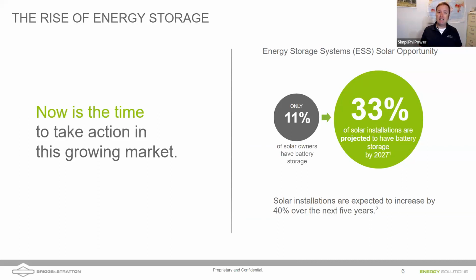That's anti-islanding, where you don't want to be producing electricity and sending it back to the grid when the grid is down, because you might electrocute a lineman trying to get the power back on in the neighborhood. So by pairing existing grid-tied solar with one of these, AC coupling it to one of our energy storage systems, we can create a microgrid for the home.